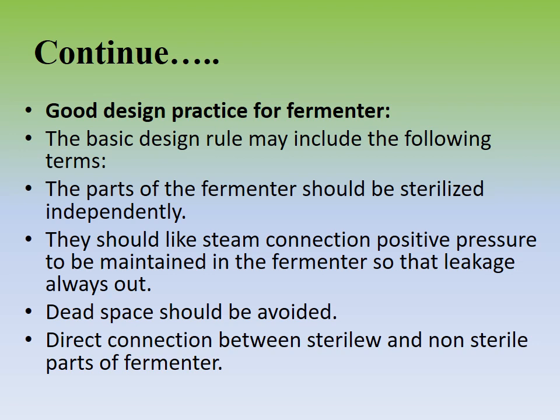Second one, positive pressure should be maintained in the fermenter so that leaks are always outward, because it is necessary to maintain this when our fermentation process is carried out, right? Next point, dead space should be avoided. And the last point, there should be no direct connection between sterile and non-sterile parts of the fermenter. Okay, so these are all about your good design practices.